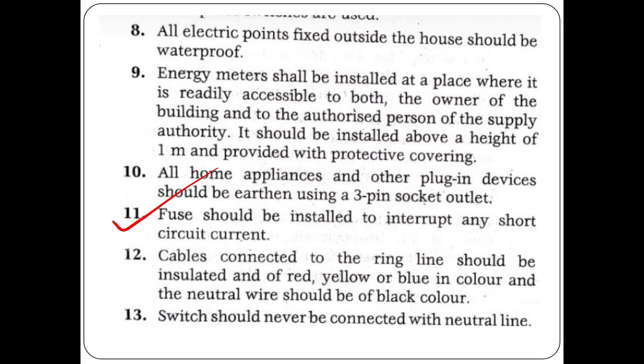Cables connected to the ring main should be insulated and red, yellow or blue in color. The neutral wire should be black in color. Switches should never be connected to the neutral wire.